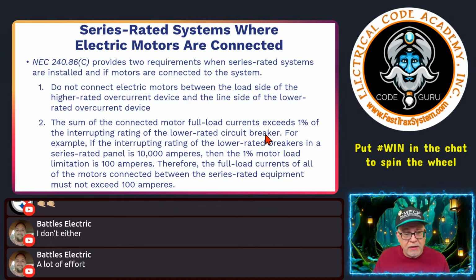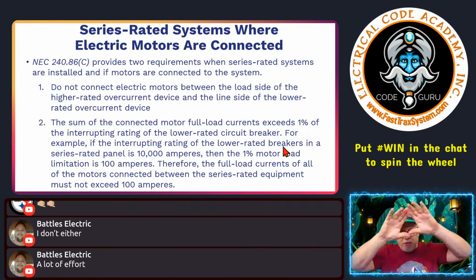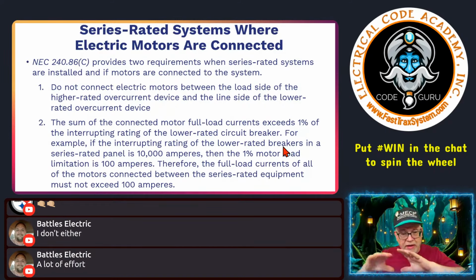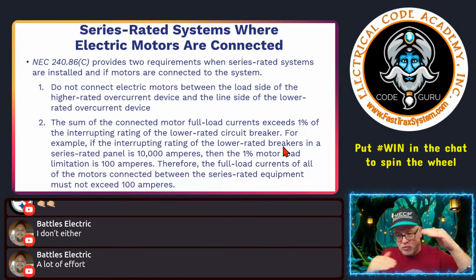So 1%. If it's a 10,000 amp, for example, what is 1%? Y'all know this without doing the math, 10,000 times 1% is 100. So 100 amps. It says the sum of the full load current exceeds 1% of the interrupting rating. So let's say you have a main breaker, then a breaker that's feeding a motor, and this one has a 10,000 amp rating on it. That's what the series rating is.